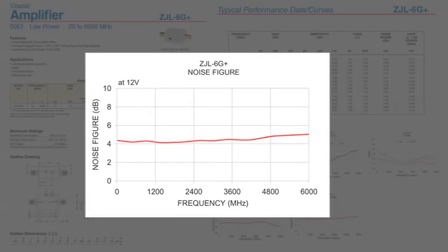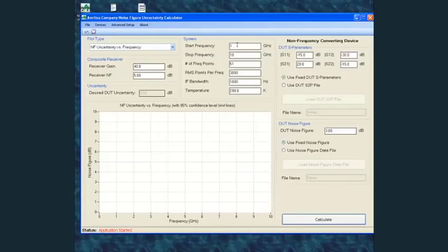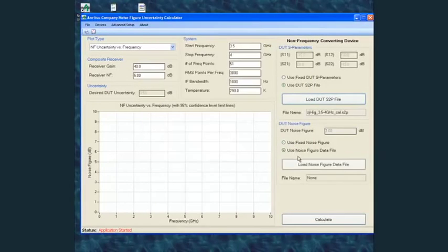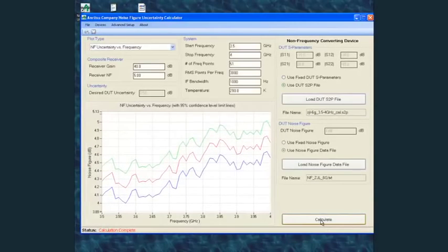In many applications, the noise figure measurement data is only part of the answer. It may be important to know the uncertainty of the measurement as well. Because there are so many possible contributors to the noise figure measurement uncertainty, Anritsu provides an uncertainty calculator. It's a standalone program that can either be run from the desktop of the VectorStar VNA or on an external PC. It provides the ability to calculate noise figure measurement uncertainty as well as determine the optimum measurement setup to achieve a desired measurement uncertainty target.